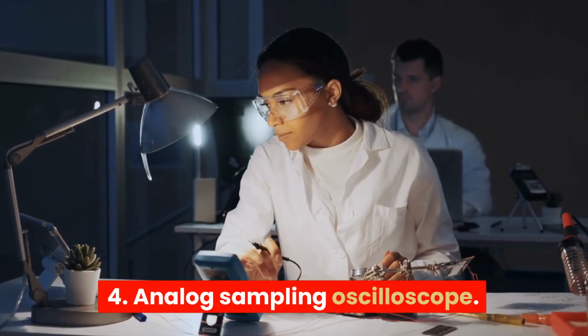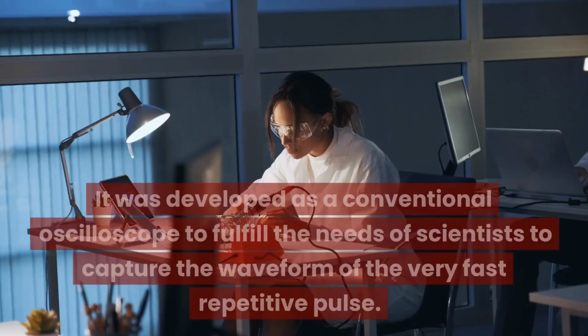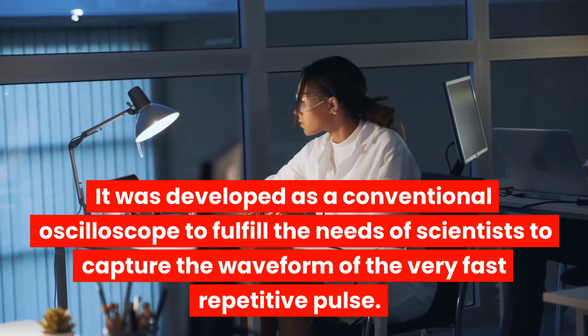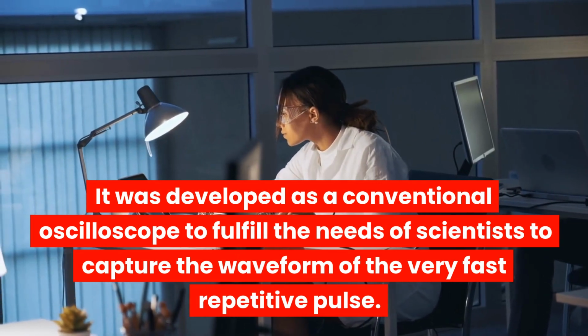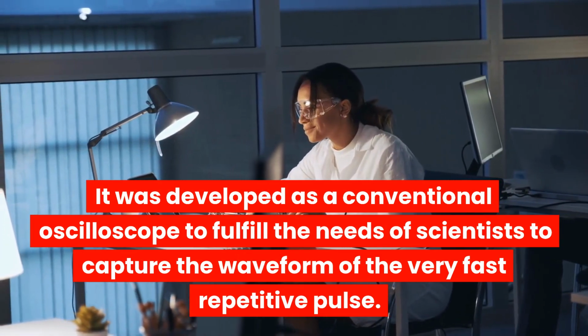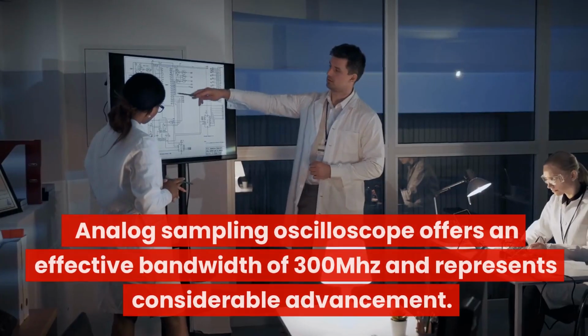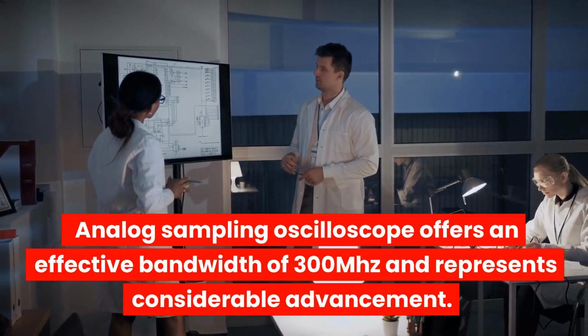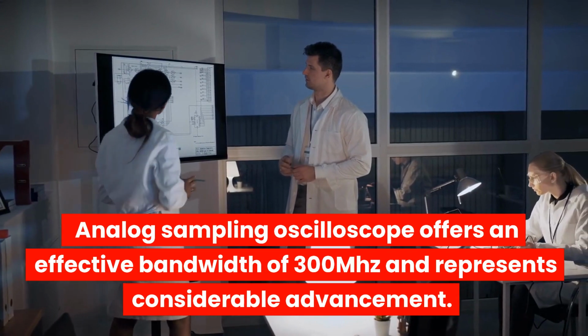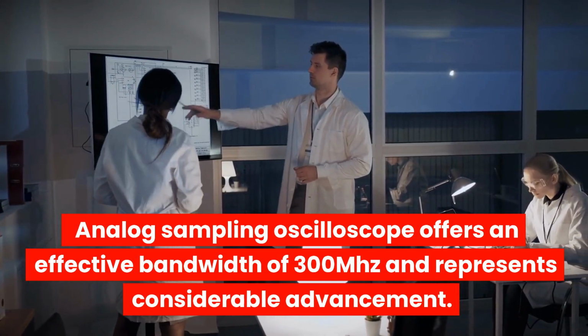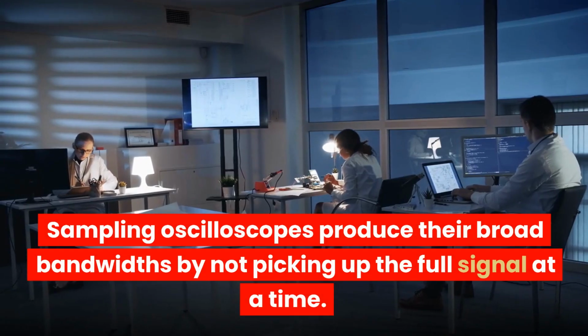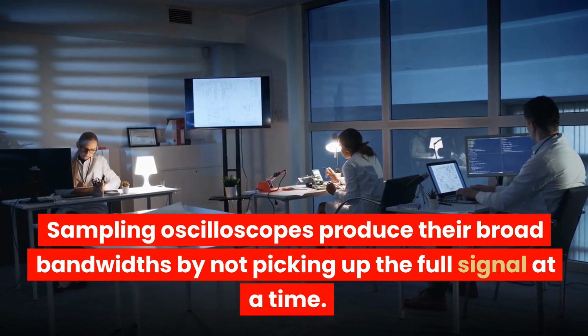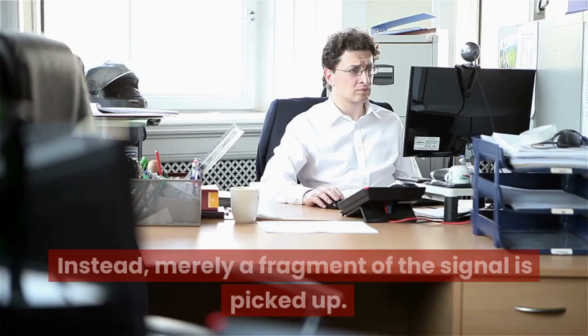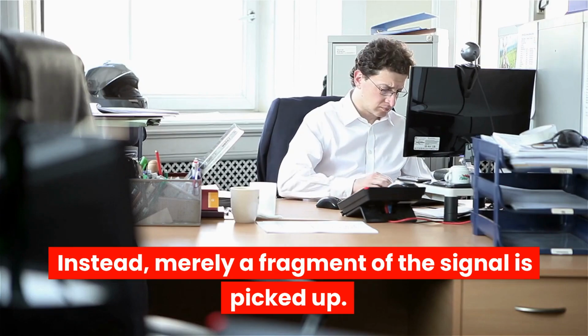4. Analog sampling oscilloscope. It was developed from the conventional oscilloscope to fulfill the needs of scientists to capture the waveform of very fast repetitive pulses. Analog sampling oscilloscope offers an effective bandwidth of 300 MHz and represents considerable advancement. Sampling oscilloscopes produce their broad bandwidths by not picking up the full signal at a time. Instead, merely a fragment of the signal is picked up.